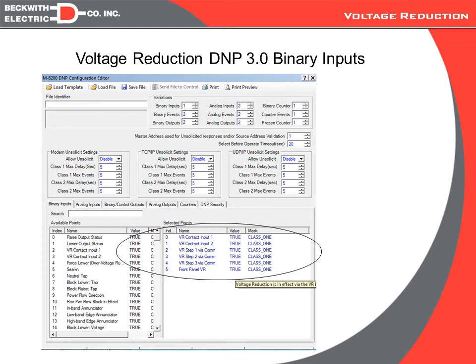Now, we're going to cover the DNP mapping in a completely different session, but we wanted to go through some of the points that are available for monitoring and controlling voltage reduction. First of all, our binary inputs are status points. So the first two we see here are the two hardware contacts. And then the next three would be the software if we were doing voltage reduction from SCADA. And the last would be via the front panel.